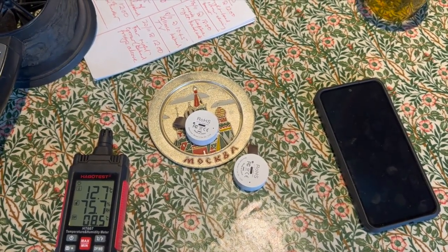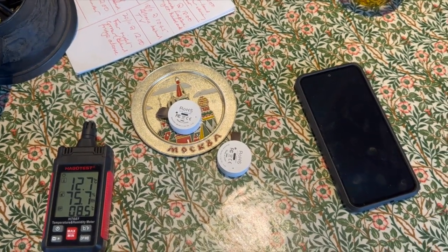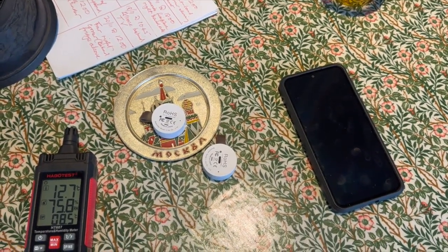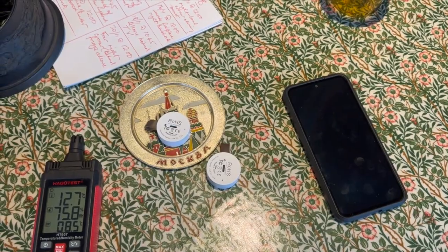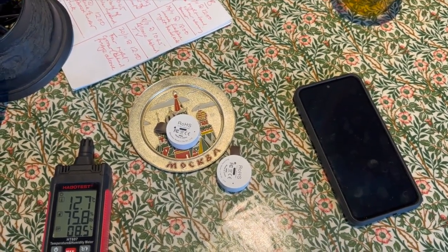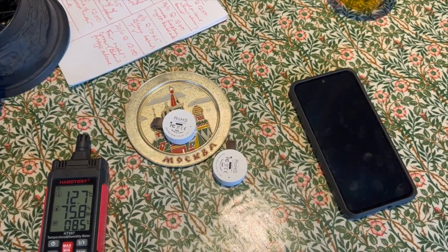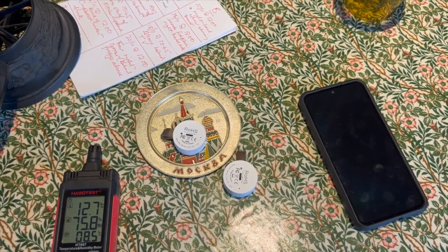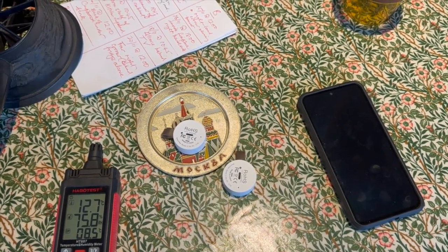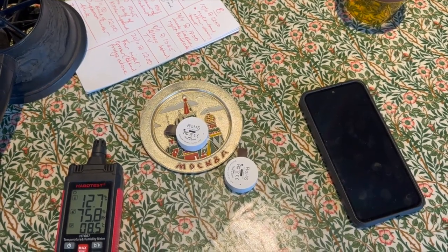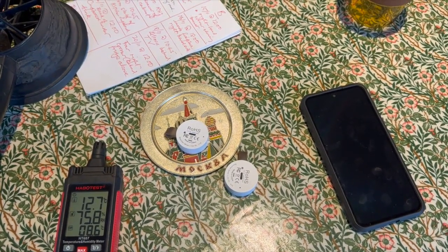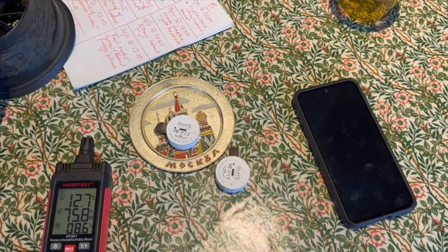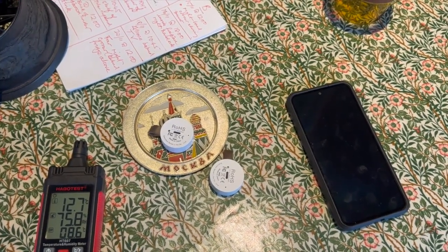The reason is for lots of different reasons that I've already put on, but this outbuilding is much colder than the rest of the property, and you're not heating it when you're not using it. So all the vapour that's coming from the rest of the property is coming into this room, and the temperature of the surface is causing high humidity, because mould only grows where relative humidity goes above 85% for long periods of time.